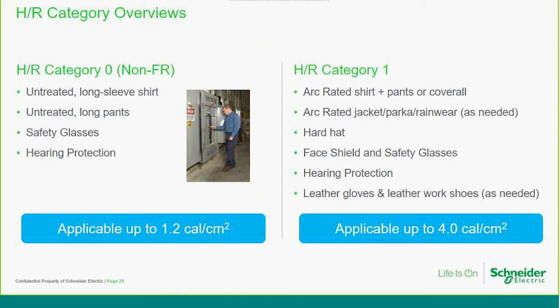So we talk about the levels. Up to 1.2 cal per square centimetre: an untreated long shirt, long pants or trousers, safety glasses, and hearing protection. That's basic resetting of miniature circuit breakers, right down in the lowest risk category as far as the operatives are concerned. And as I said, a lot of companies are using that at control panel levels.